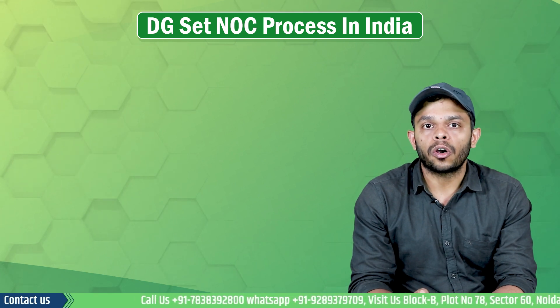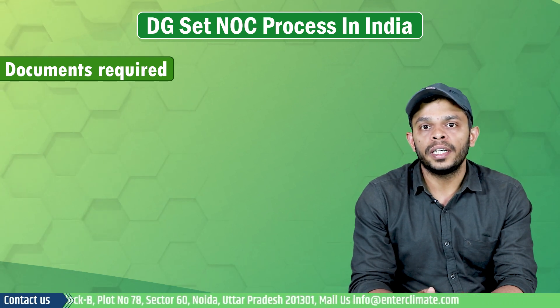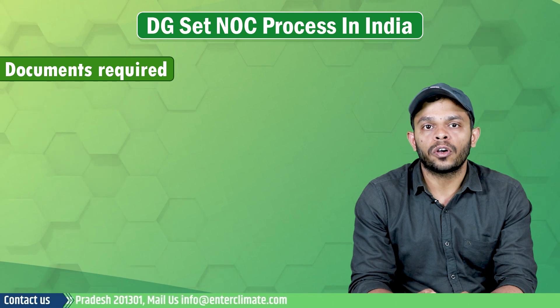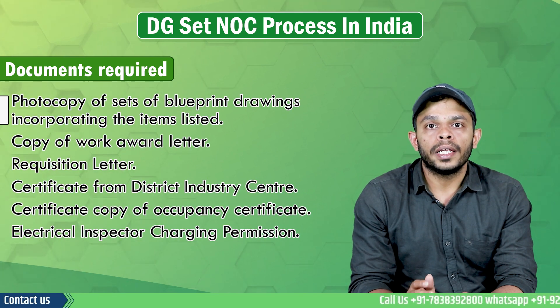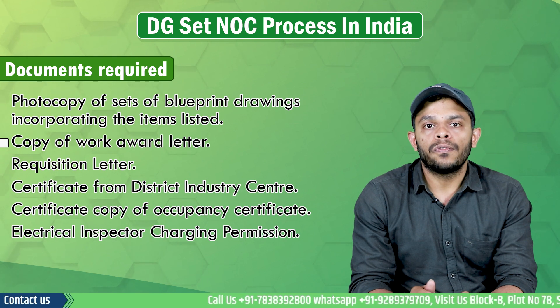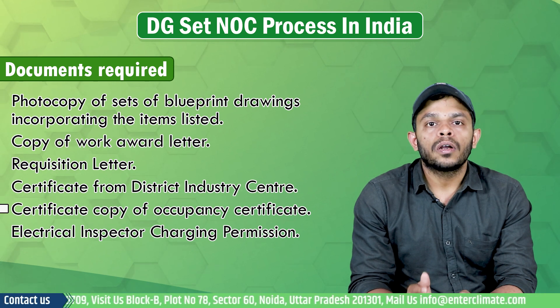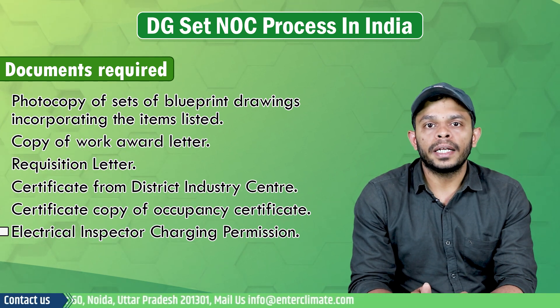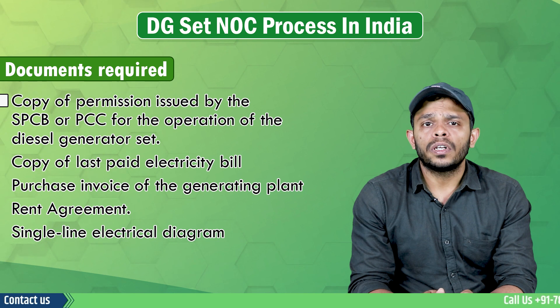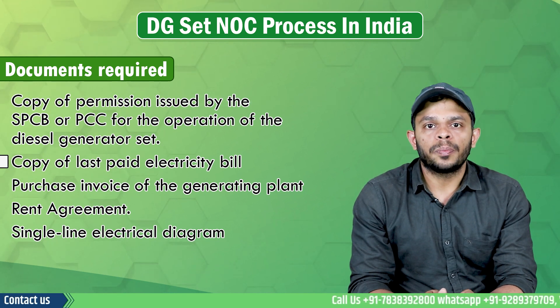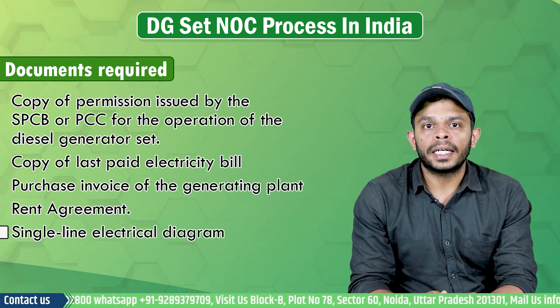Let's now see what documents are required for this NOC. The application for DG set installation must be submitted to the electrical inspectorate with relevant documents and drawings, including: photocopy sets of blueprint drawings, copy of work award letter, requisition letter, certificate from district industry centre, certificate copy of occupancy certificate, electrical inspector charging permission, copy of permission issued by the SPCB or PCC for the operation of the DG set, copy of last paid electricity bill, purchase invoice of the generating plant, rent agreement, and a single line electrical diagram.